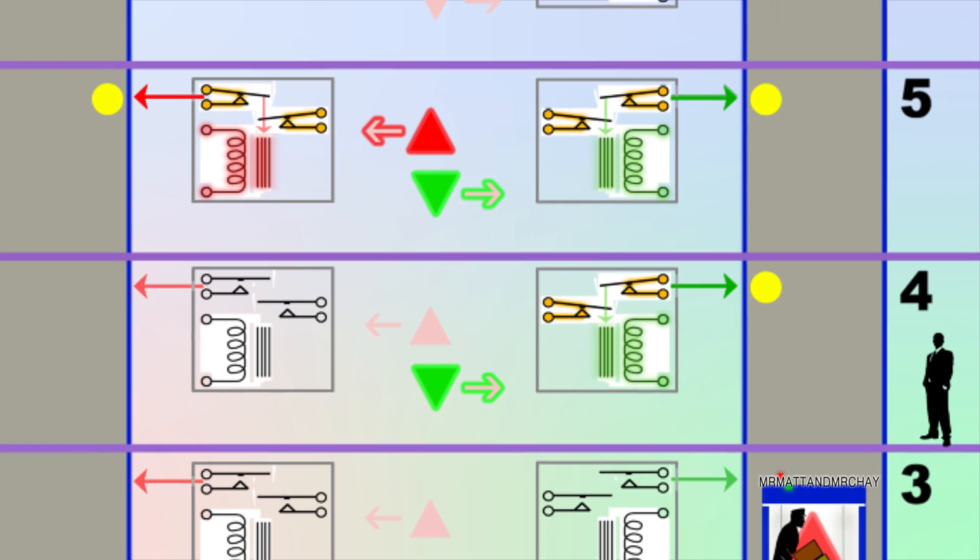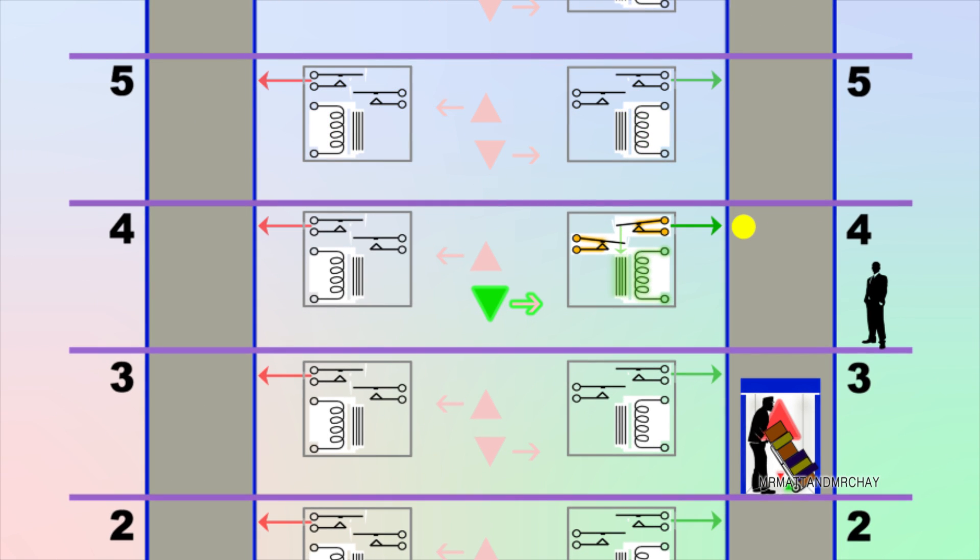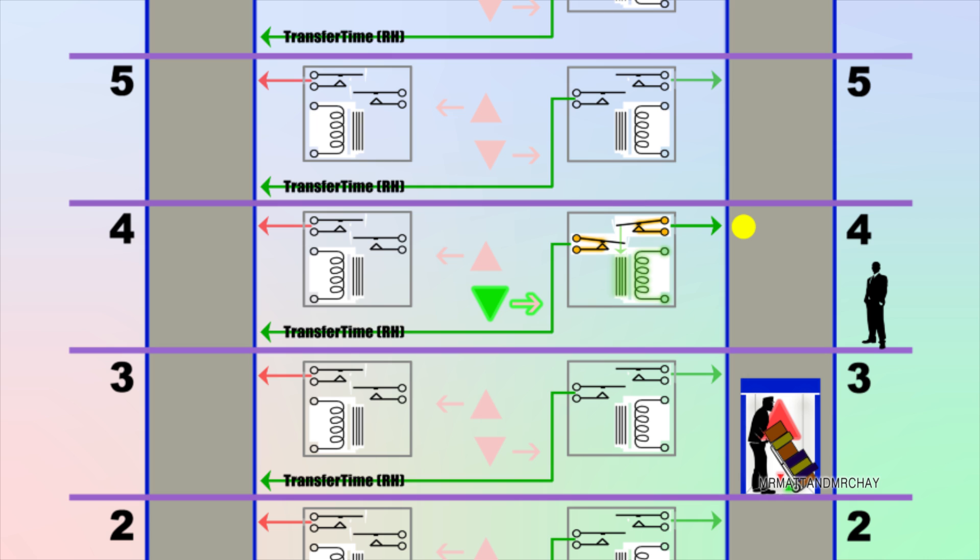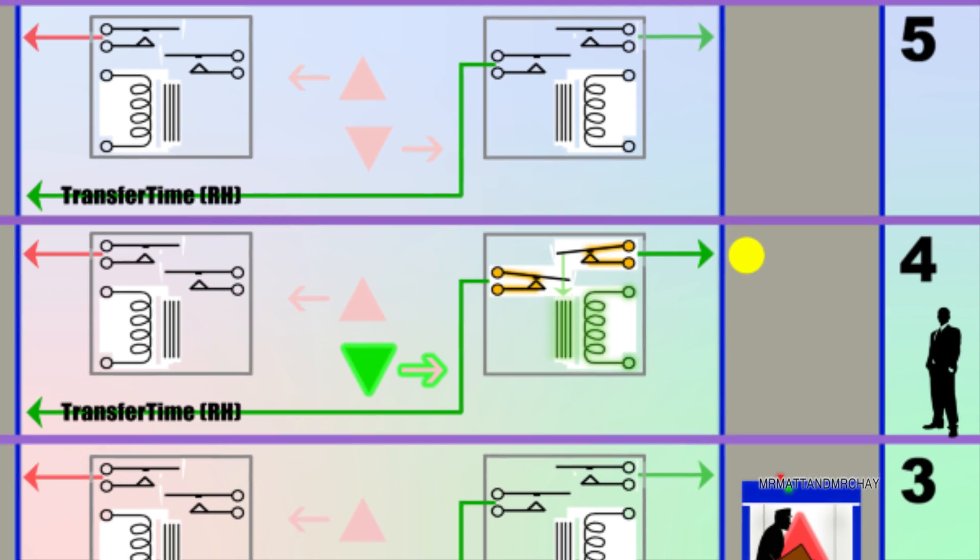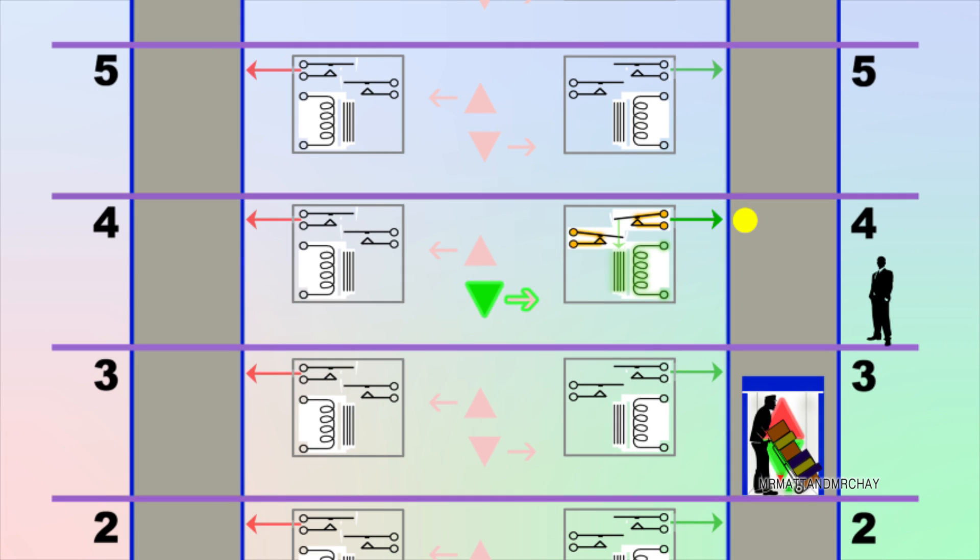When lift B is blocked open, or switched to inspection mode, or simply switched off, the down calls must be redirected to the other lift. This is the job of TT relay, transfer time. Now, the second set of contacts is connected to the other lift. This also works the other way around. If the left lift is not available, then the up calls are connected to the right lift.